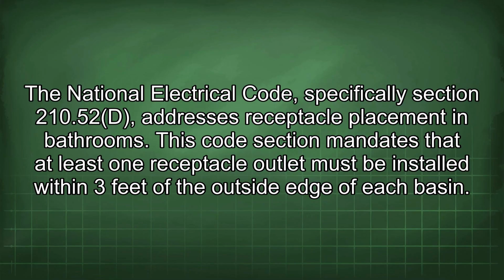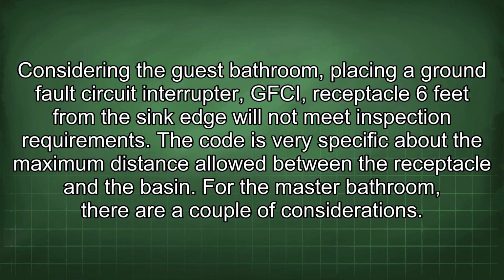The National Electrical Code, specifically Section 210.52(D), addresses receptacle placement in bathrooms. This code section mandates that at least one receptacle outlet must be installed within 3 feet of the outside edge of each basin. Considering the guest bathroom, placing a ground fault circuit interrupter (GFCI) receptacle 6 feet from the sink edge will not meet inspection requirements. The code is very specific about the maximum distance allowed between the receptacle and the basin.